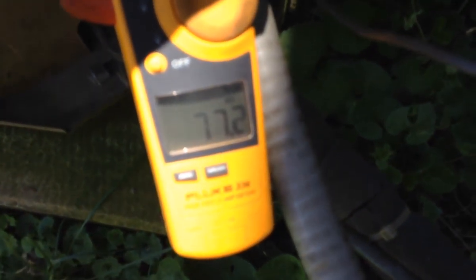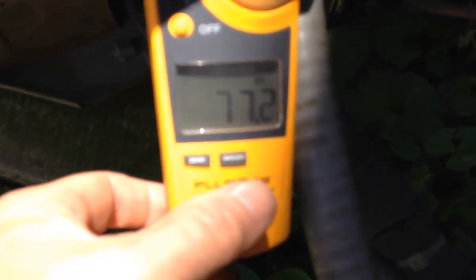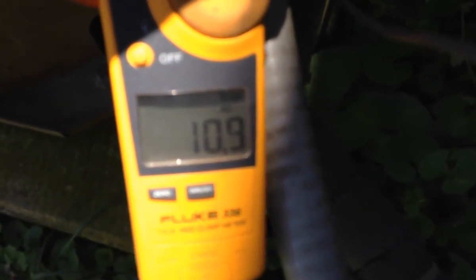Okay everyone, so I turned the thermostat on and you can see that it recorded a 77.2 inrush. Now, I'm just going to turn that off and see what amperage it normally uses. So you can see right there, after the inrush I'm using about 11 amps.